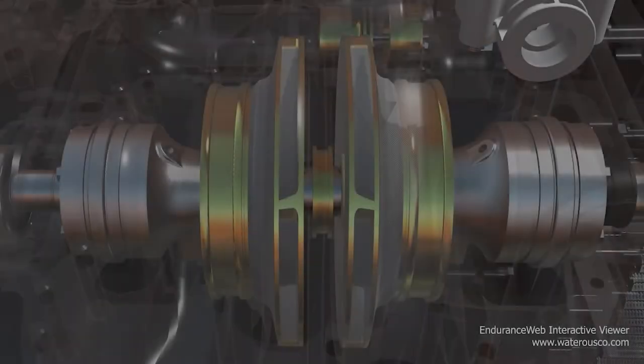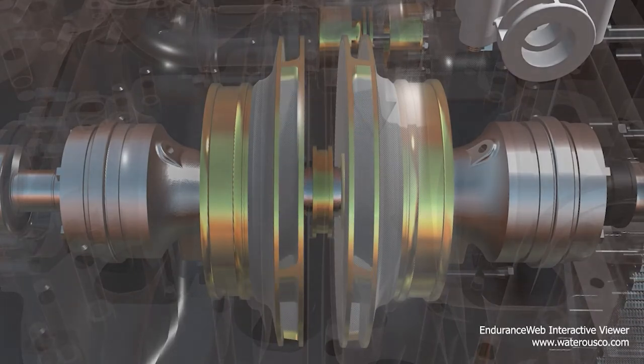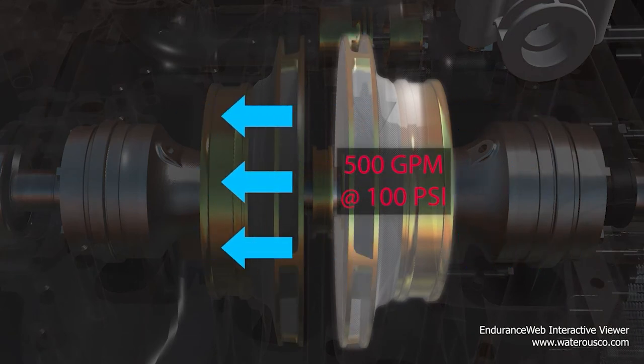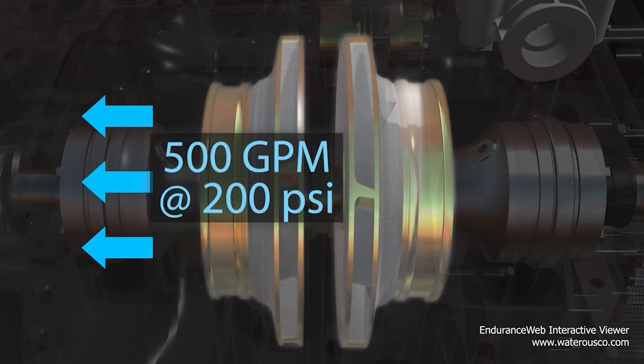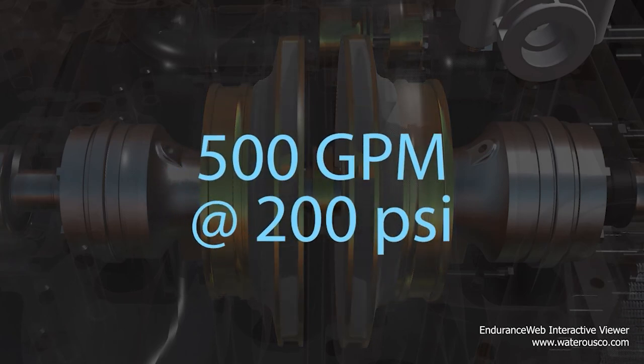The pressure is increased while operating at the same RPM as it was in volume mode. The first stage impeller increases the velocity and pressure of water, directing it to the second stage, where additional velocity and pressure are added. This results in the same volume of water at double the pressure.